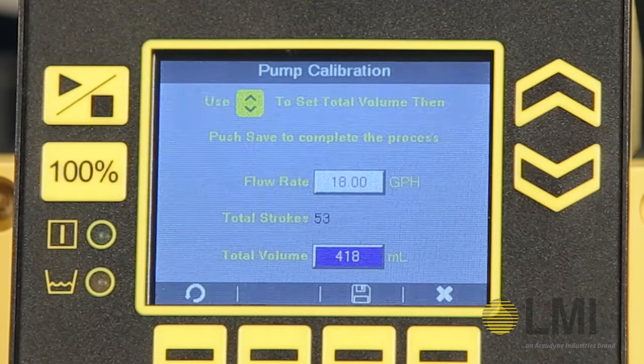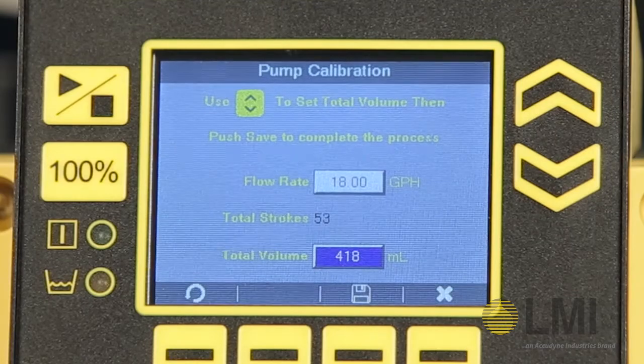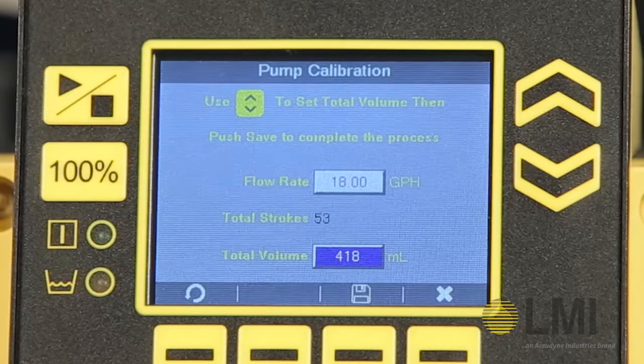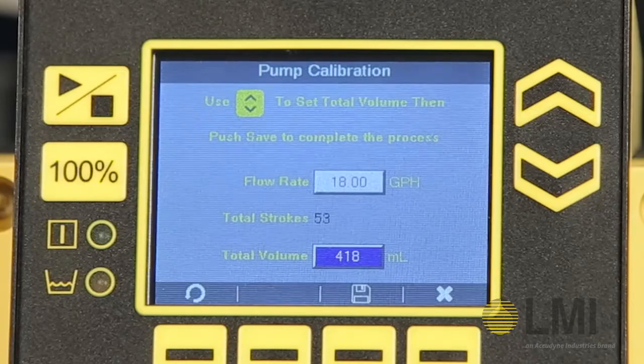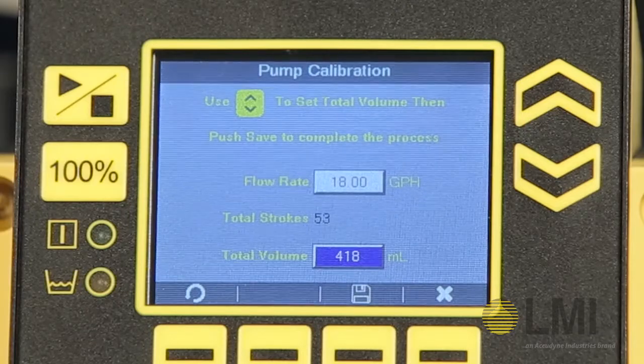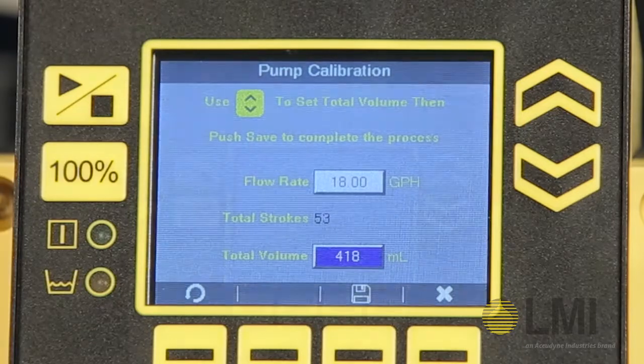With the pump stopped, you can now review the calibration settings. In this example, we will use the flow rate identified on our screen of 18 gallons per hour. The total stroke count is 53, with a total volume of 418 milliliters.